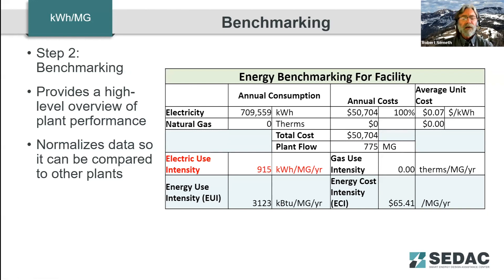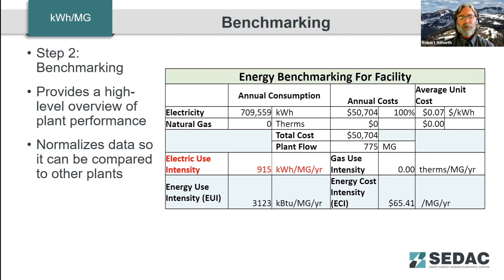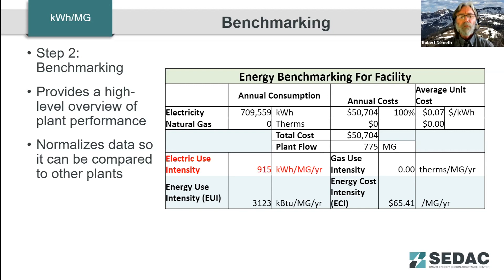We take that information and create a benchmarking table. Of particular interest is the electric use intensity, highlighted in red — it's kilowatt hours per million gallons per year. It tells us how well a plant is performing. This one's at 915 kilowatt hours per million gallons per year, which is very good. You'll see very soon that there are much higher numbers we encounter. This provides a high-level overview and normalizes the data so we can compare one plant to another.